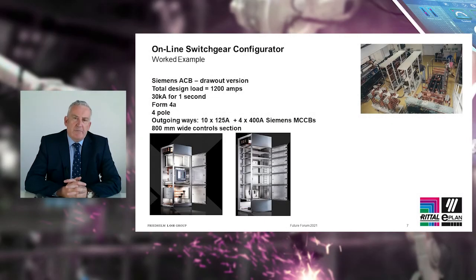This is a worked example just to show you how the configurator works online. The basic information you can see there. Because we're designed to the latest standards, we need to know the switchgear manufacturer: Siemens, ABB or Schneider. For this exercise we're using Siemens. As you can see from the picture there, we have a test lab in Germany, and we use independent test stations where we do heat rise tests for the circuit breakers. And the configurator is intelligent enough to calculate which circuit breaker and the maximum current you can get from the ACB.